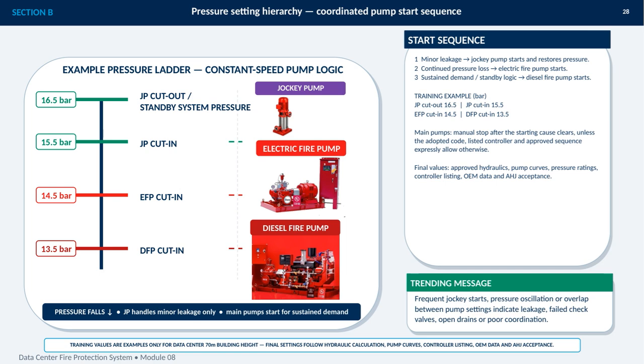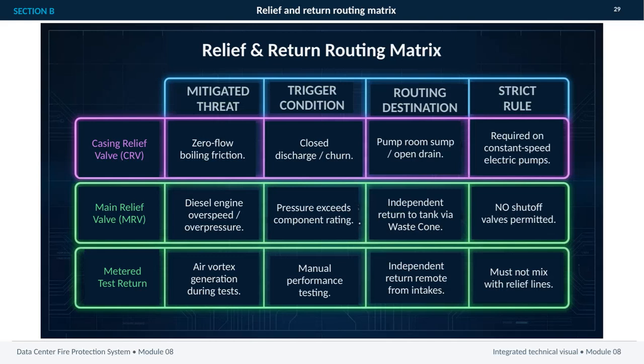Frequent jockey starts, pressure oscillation, or overlapping pump operation should prompt investigation of leakage, failed check valves, open drains, or poor coordination. This matrix defines how different relief and return functions are triggered, where they discharge, and which rules control their installation. The key principle is that each function has a dedicated routing path and must remain properly separated.